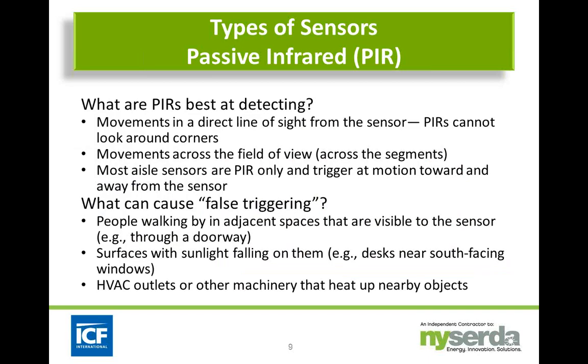And passive infrared, as I mentioned a minute ago, detects heat motion, but this is a direct line of sight type of device. It can't see around corners. So if you have an odd space, you have equipment in the way, you have all kinds of intersections in a hallway, you want to consider not necessarily using passive infrared because it can't see around corners. The movement has to be across the field of view, which is those segments that we showed a minute ago.